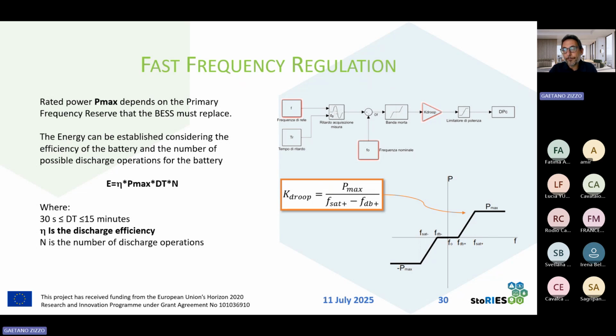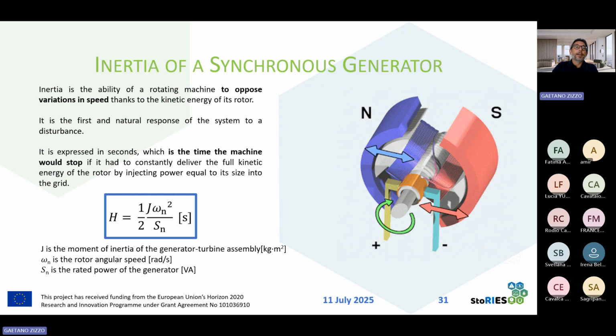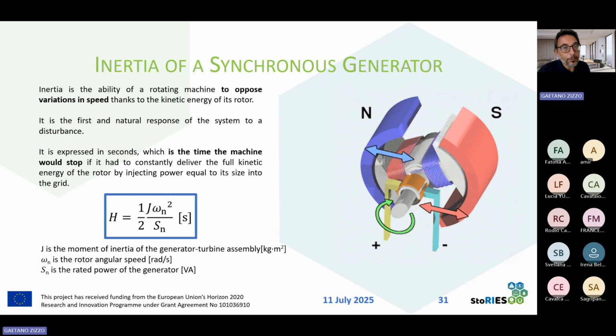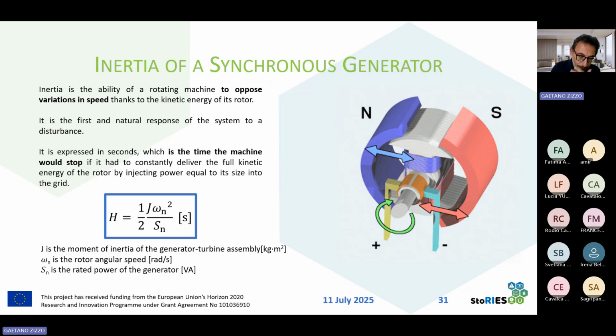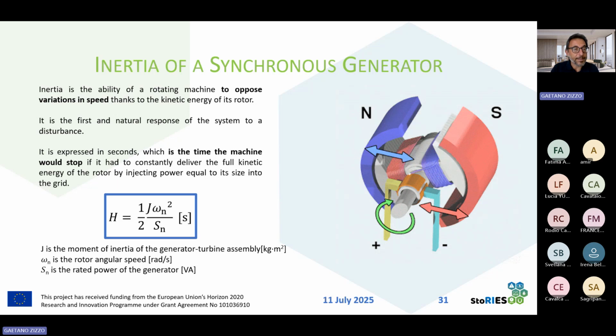Then, in this way, we have found the total power that must be installed for having a desired maximum steady state variation at the end of a given disturbance. But the number of storage systems that must be installed depends on various factors. So this can be defined by the TSO, or can be asked to various users to install a given power for delivering this service. Another important service that is usually coupled to fast frequency regulation is virtual inertia. So the batteries can be used for providing virtual inertia.